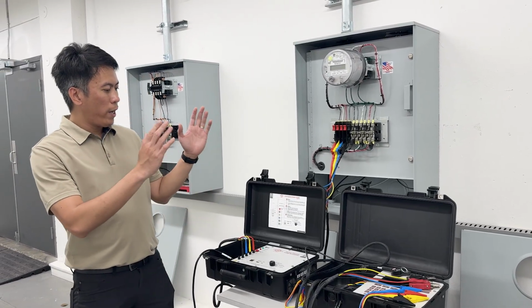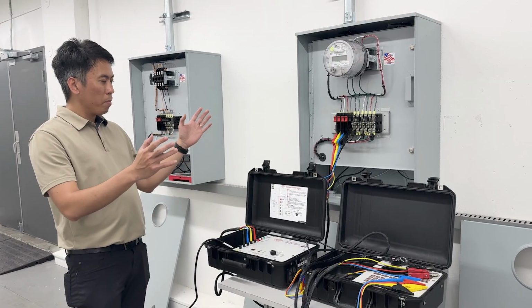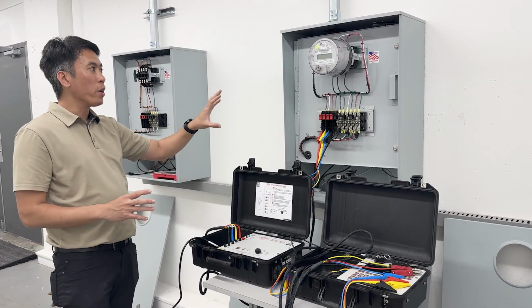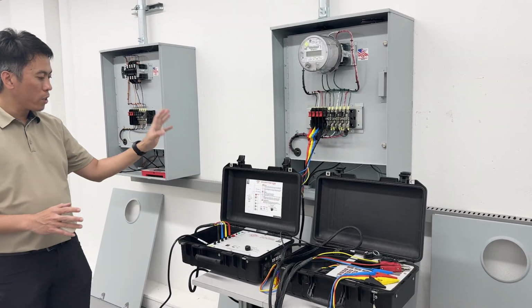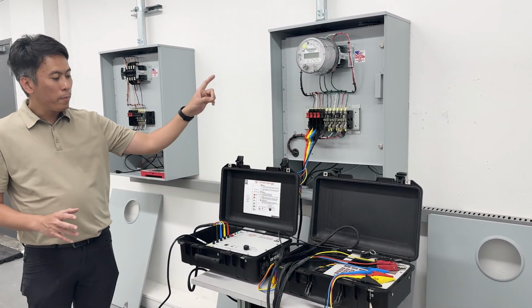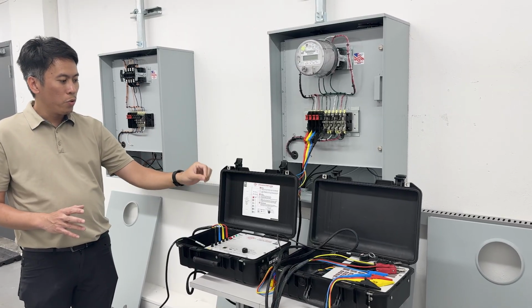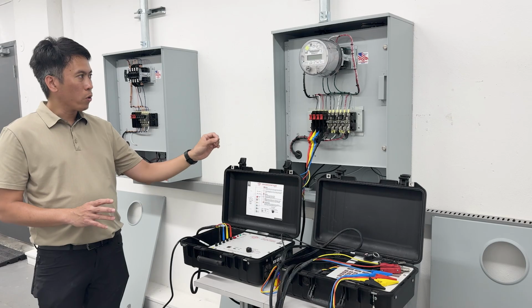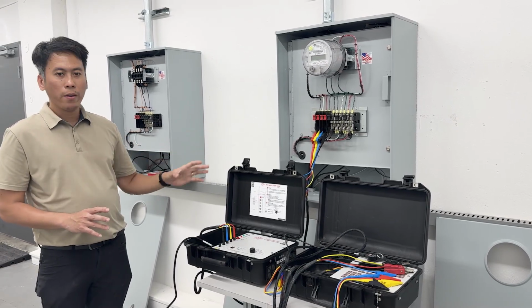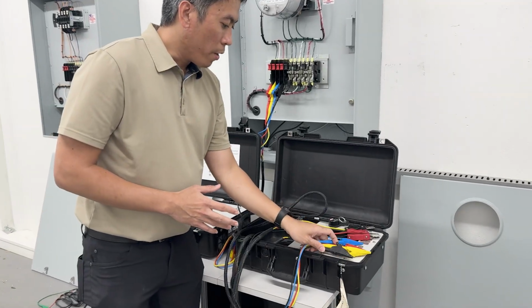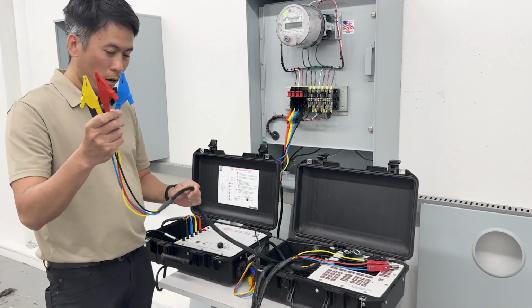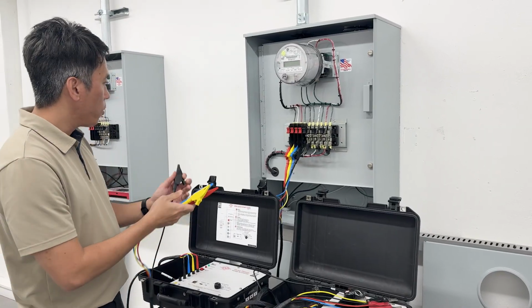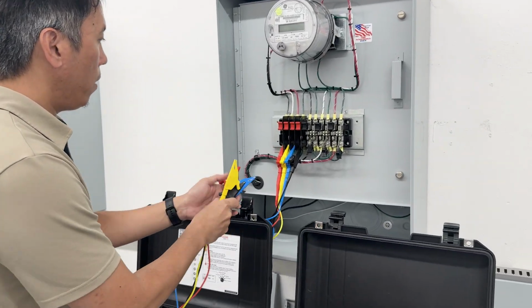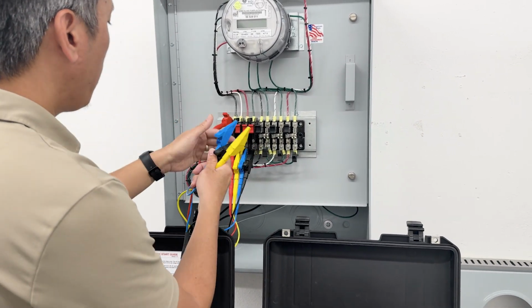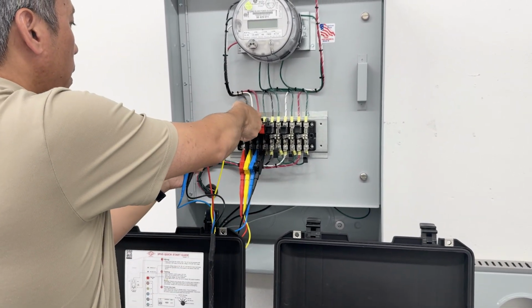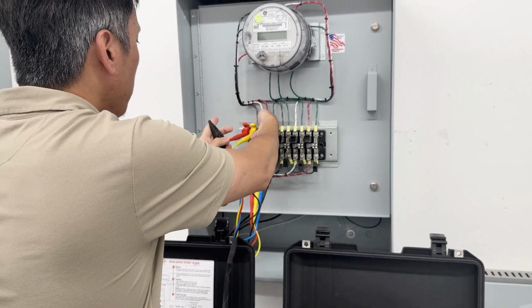Okay, so we have here a setup of an intertie meter test. So let's just pretend this is an intertie meter in a substation somewhere, and we're gonna use the 6440 voltage synthesizer to power up the meter, and then use the 6330. The 6330 measures the voltage and the current of the accuracy of the meter. Okay, so the first step is we would connect this voltage cable set. I'm just going to line it up with the test switch. Put it on top. Red, yellow, blue, and black.